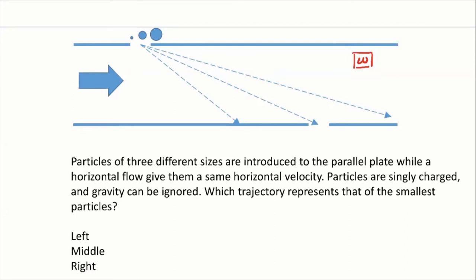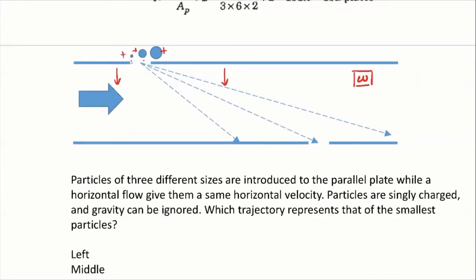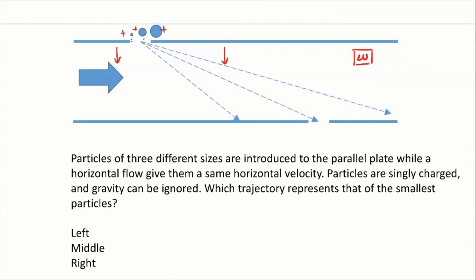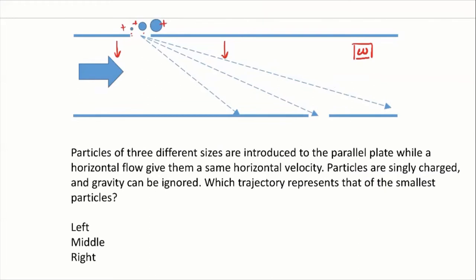When we measure particle size distributions, what we do is charge these particles — no matter what their size, we give them only a single charge. No matter how large they are, a device can give them just a single charge. If they have a single charge, we can calculate the migration velocity of the particle in the electrostatic field. This is called the electrostatic classifier.